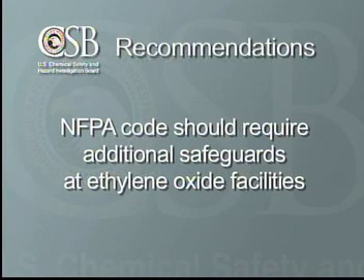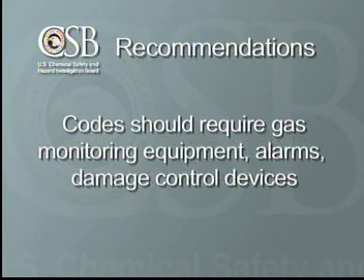The CSB recommended that the National Fire Protection Association, which creates fire codes used around the country, require additional safeguards to prevent explosions at ethylene oxide facilities. Specifically, we recommended the codes require the use of gas concentration monitoring equipment, alarms, and explosion damage control devices.